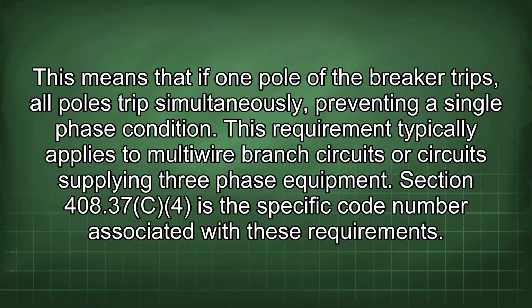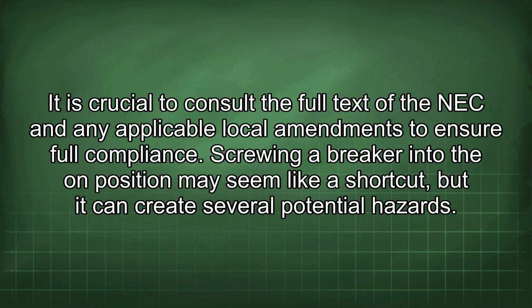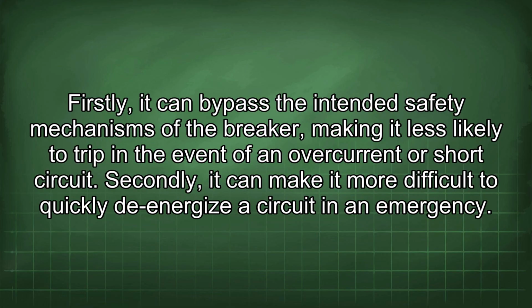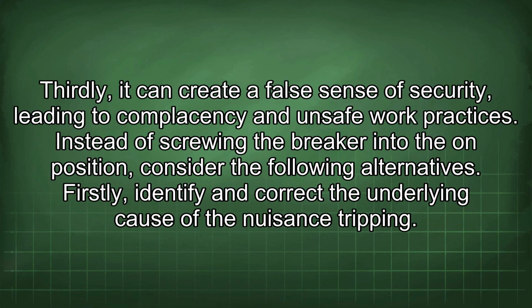Section 408.37c4 is the specific code number associated with these requirements. It is crucial to consult the full text of the NEC and any applicable local amendments to ensure full compliance. Screwing a breaker into the on position may seem like a shortcut, but it can create several potential hazards. Firstly, it can bypass the intended safety mechanisms of the breaker, making it less likely to trip in the event of an overcurrent or short circuit. Secondly, it can make it more difficult to quickly de-energize a circuit in an emergency. Thirdly, it can create a false sense of security, leading to complacency and unsafe work practices.